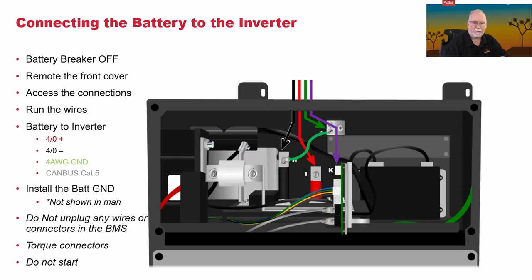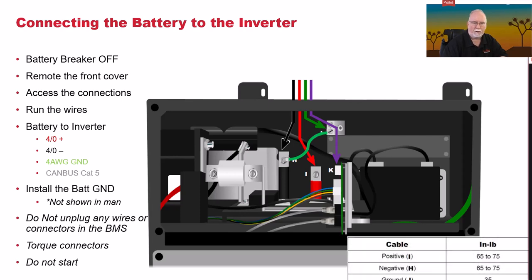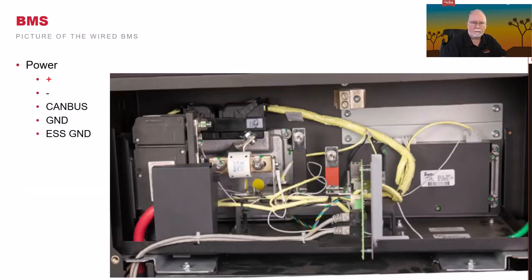And then finally we have the purple wire, which is our CAN bus connection. All the cables need to be torqued properly, the positive and negative between 65 and 75 inch-pounds, the ground to 35 inch-pounds, that's both ground connections. I'll show you what it actually looks like in reality. This is a non-populated cabinet. So you see my negative terminal standing up here, positive terminal standing up here, my ground, which goes to the chassis here, and then my connection where my CAN bus would go.